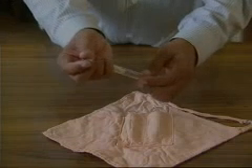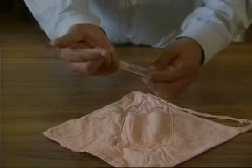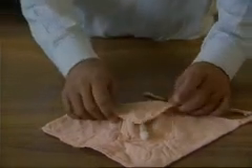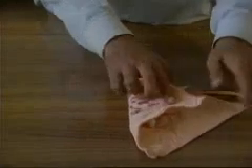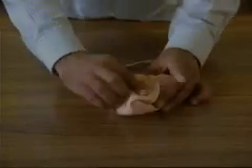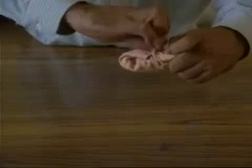While packing the material for sterilization in an autoclave, we should keep two things in mind. Firstly, it should be packed in such a way that it allows steam to enter and air to escape from the packet.